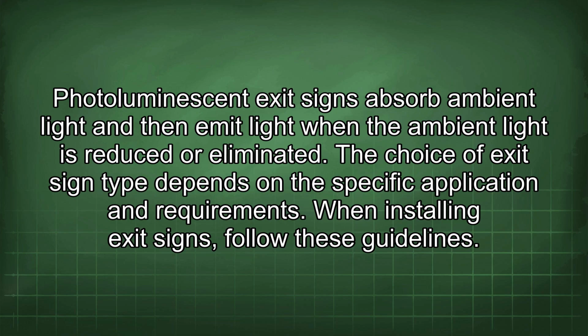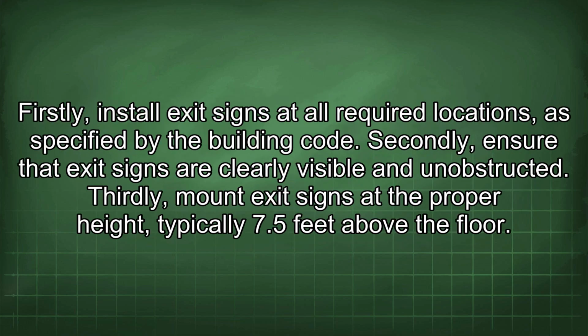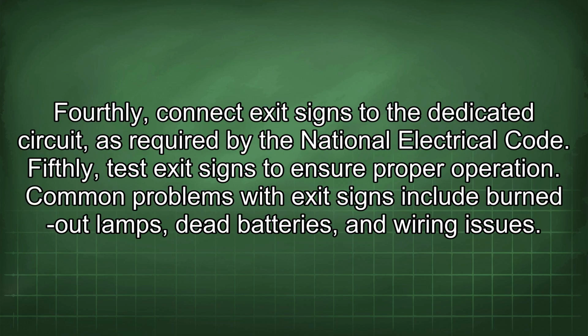When installing exit signs, follow these guidelines. Firstly, install exit signs at all required locations, as specified by the building code. Secondly, ensure that exit signs are clearly visible and unobstructed. Thirdly, mount exit signs at the proper height, typically 7.5 feet above the floor. Fourthly, connect exit signs to the dedicated circuit as required by the National Electrical Code. Fifthly, test exit signs to ensure proper operation.